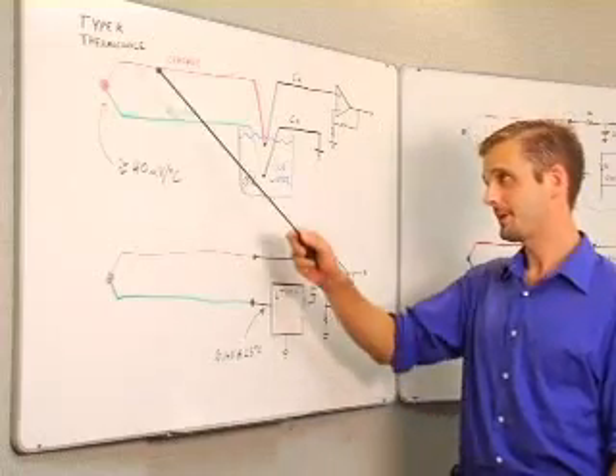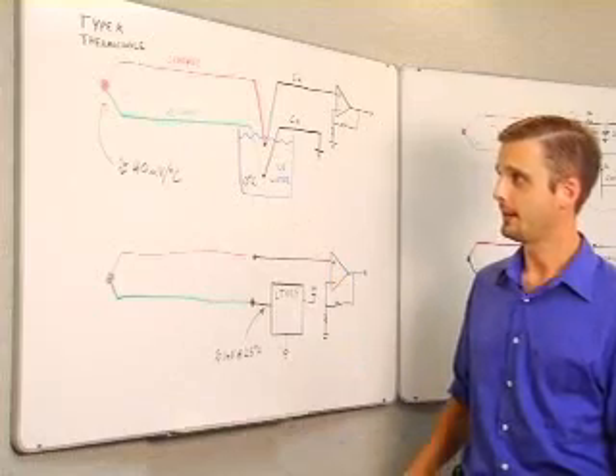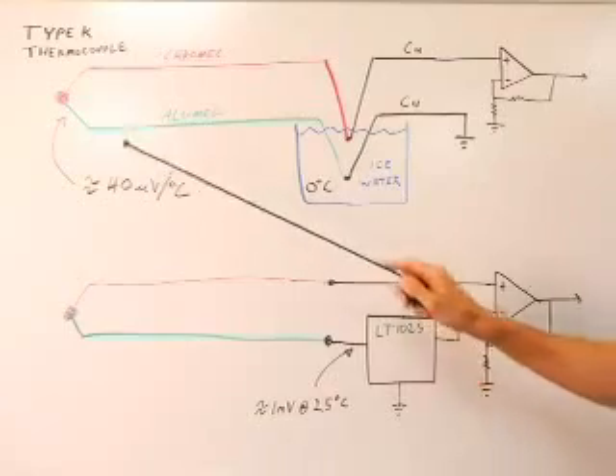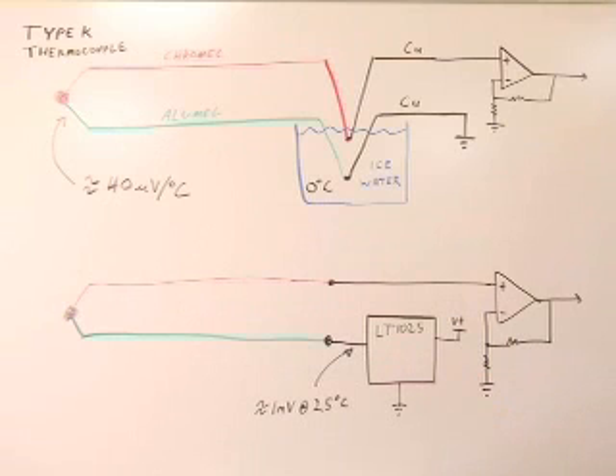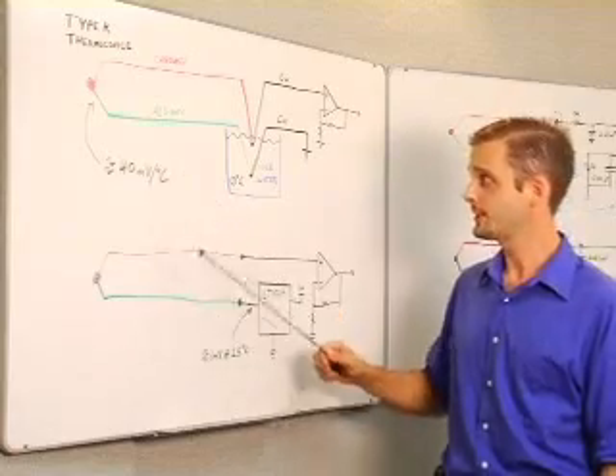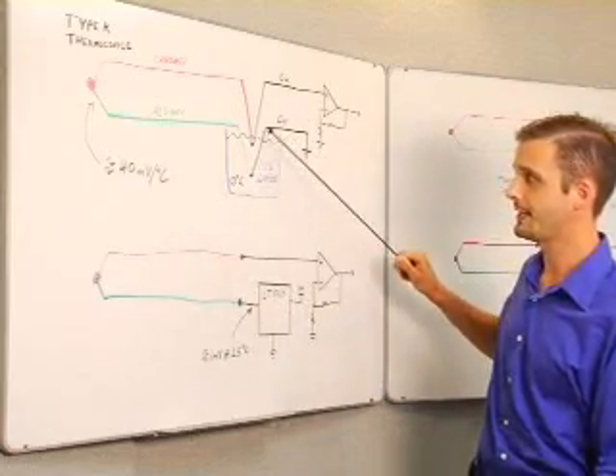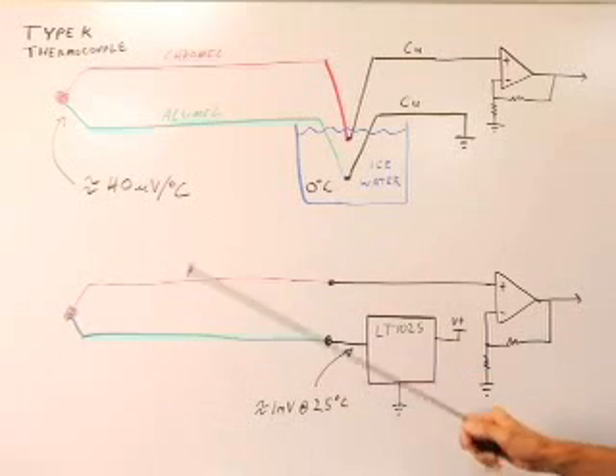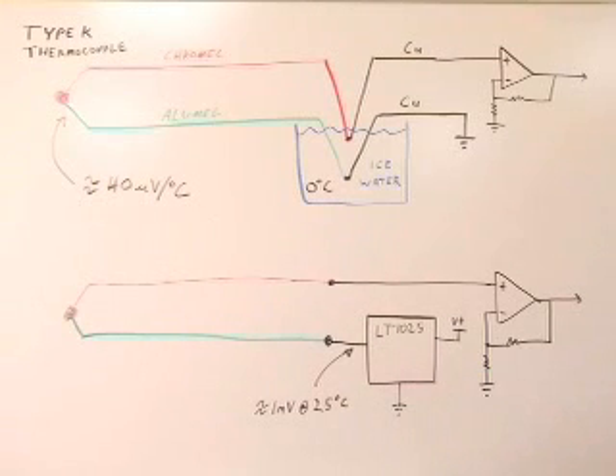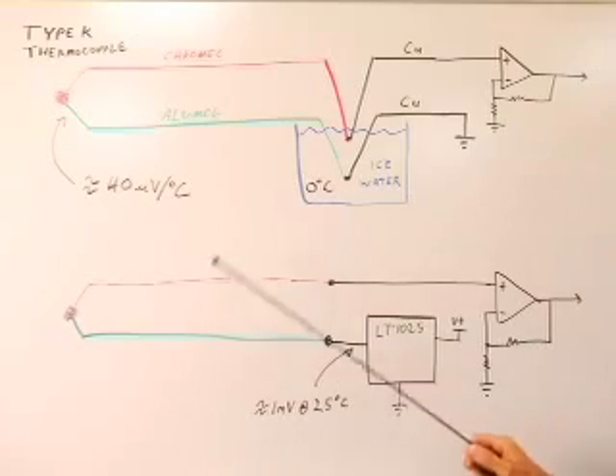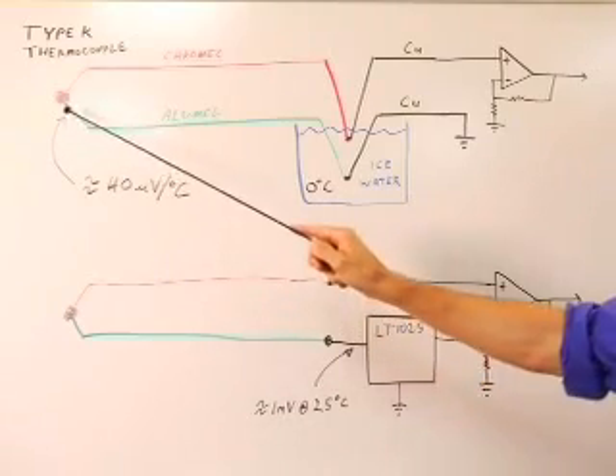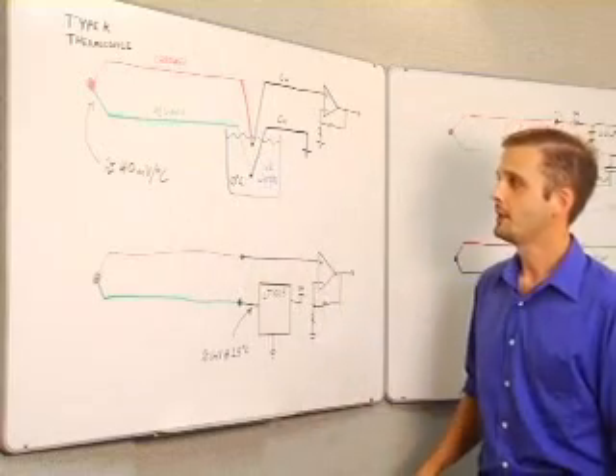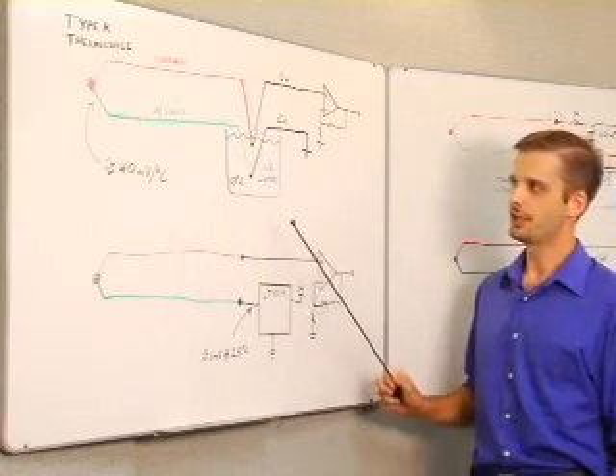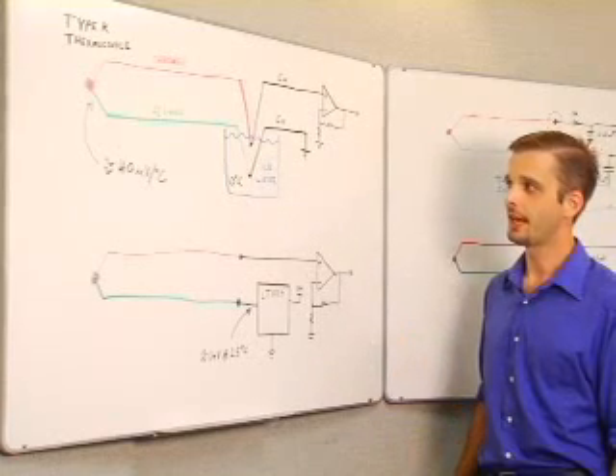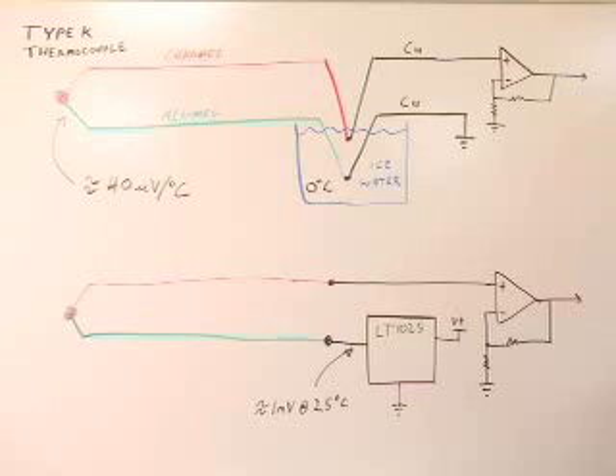So here's a schematic of how a Type K thermocouple would typically be applied. The way a thermocouple works is it's two dissimilar metals in which a temperature gradient along the wires produces a voltage gradient. And the two different materials have different gradients that result in a net voltage difference at the cold end of the thermocouple. So a Type K thermocouple has an output of approximately 40 microvolts per degree C. And that's the difference between the hot end of the thermocouple and the cold end. So the classic way of dealing with the cold junction is to actually submerge the cold junction in an ice bath to hold it at 0 degrees C, so there's no offset term.